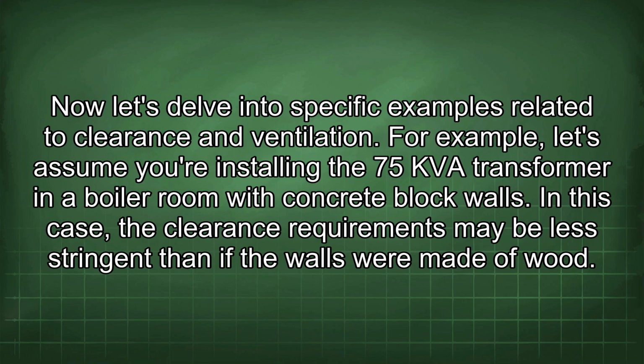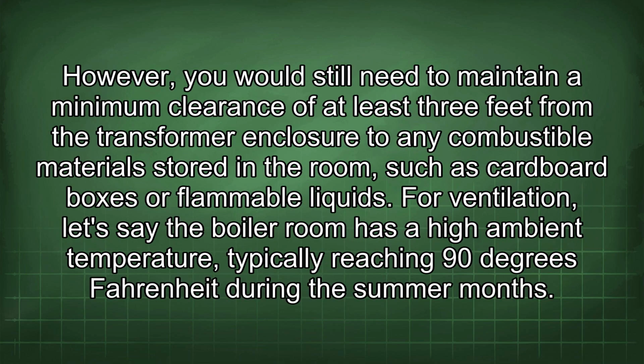For example, let's assume you're installing the 75 kVA transformer in a boiler room with concrete block walls. In this case, the clearance requirements may be less stringent than if the walls were made of wood. However, you would still need to maintain a minimum clearance of at least 3 feet from the transformer enclosure to any combustible material stored in the room, such as cardboard boxes or flammable liquids.